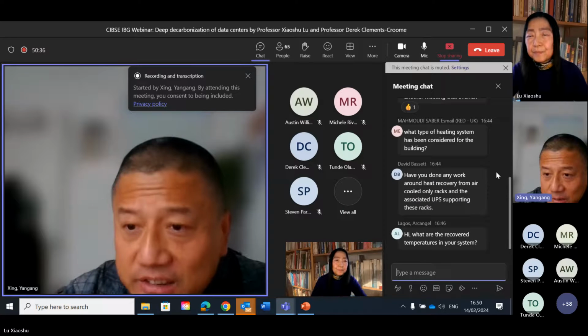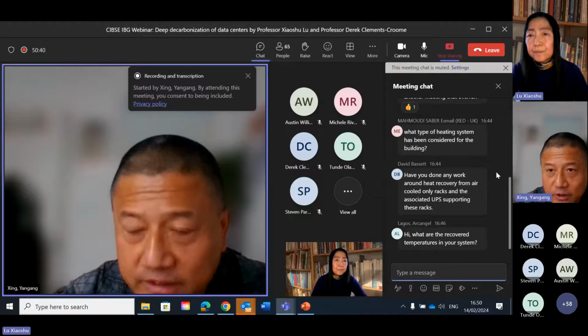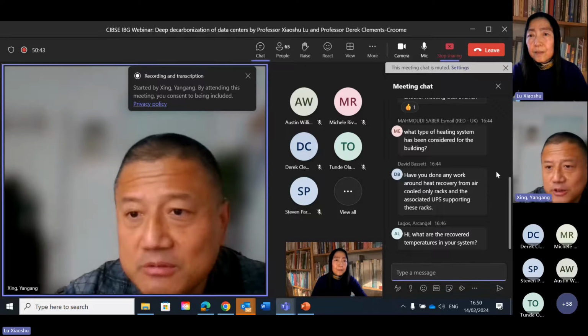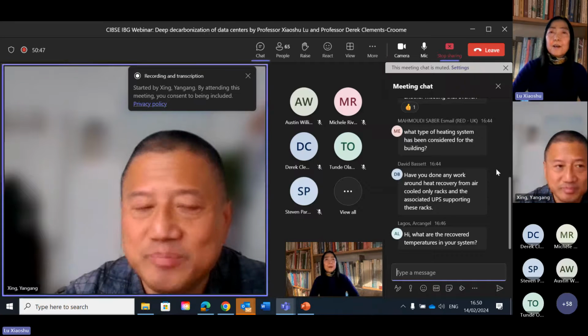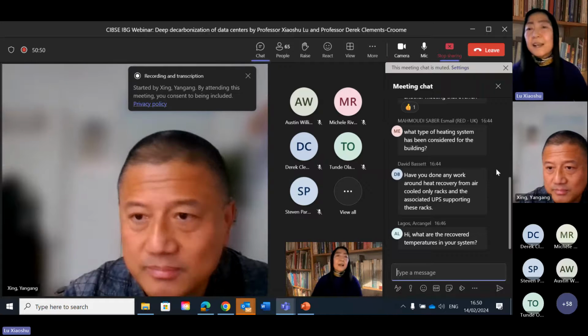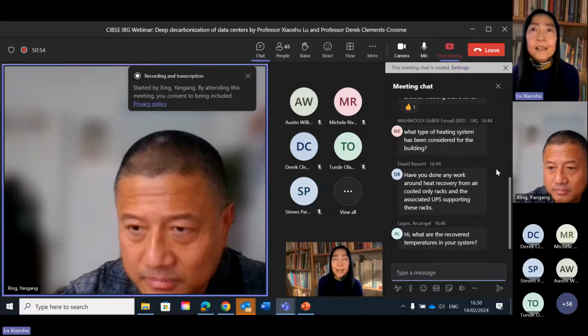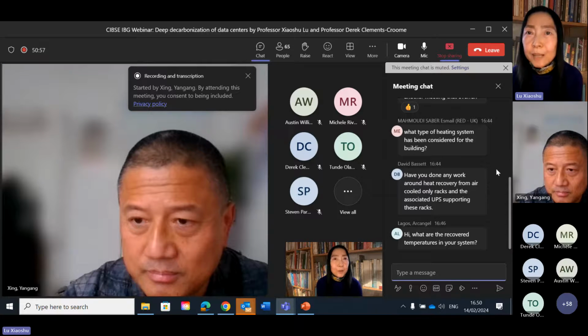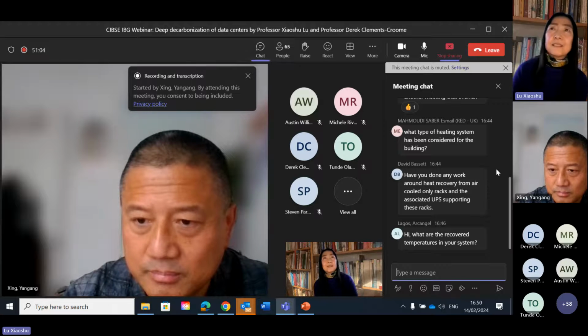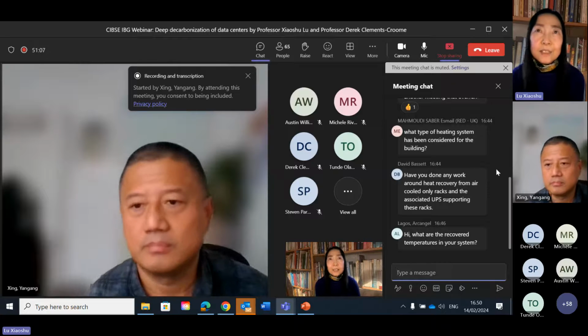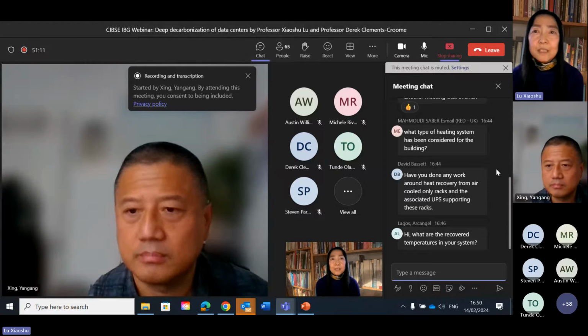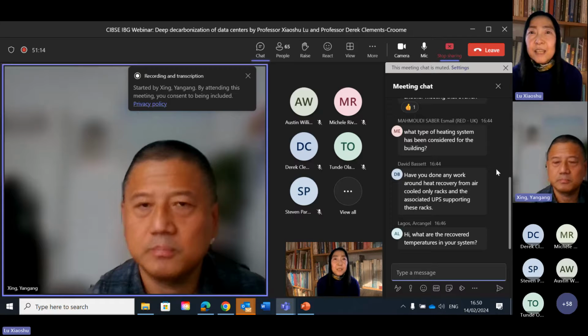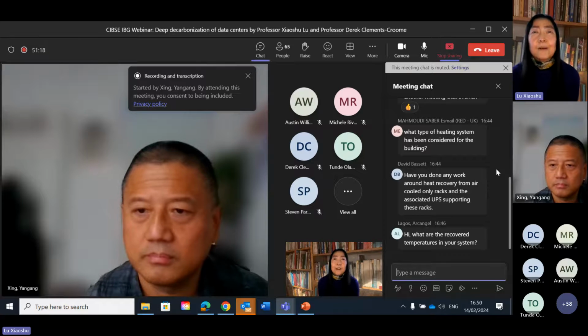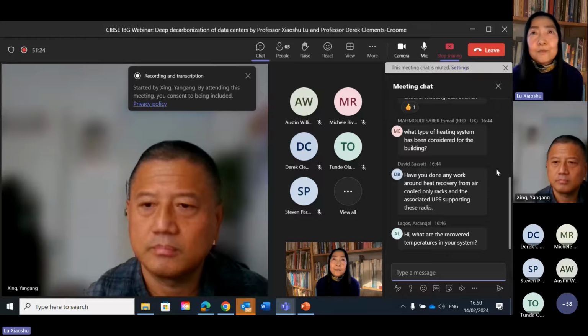Sorry, okay I'll read it out: what type of heating system has been considered for the building? So it's for the building heating, is that what you're asking? Talking about, if we talk about waste heat recovery, any heating system can be utilized. The only requirement is the return temperature should be, let's say, because the supply temperature is about 60, so in a practical point of view, it should be maybe 20 degrees lower. Or in theory, 10 degrees, okay, but if we talk about practical things, you never know this 10 degrees, so it should be 45, 40 degrees, okay.